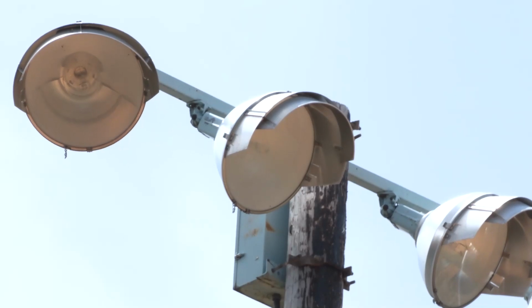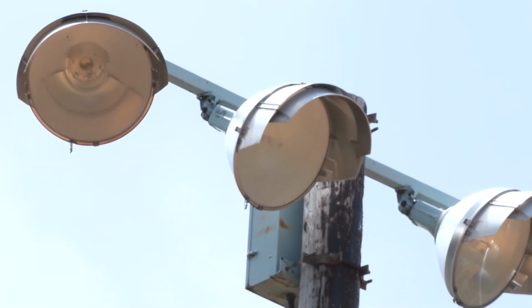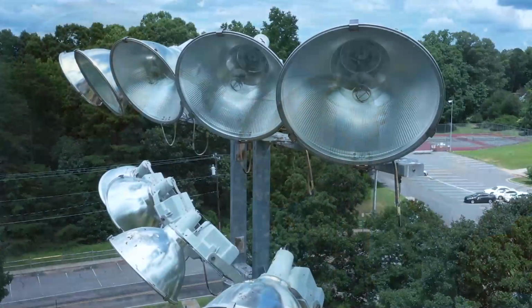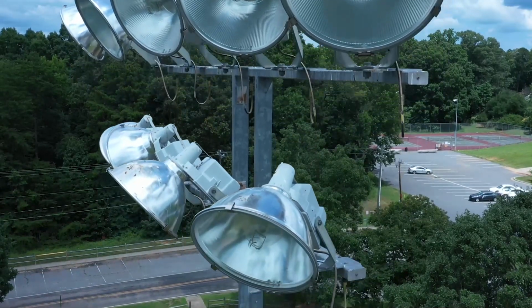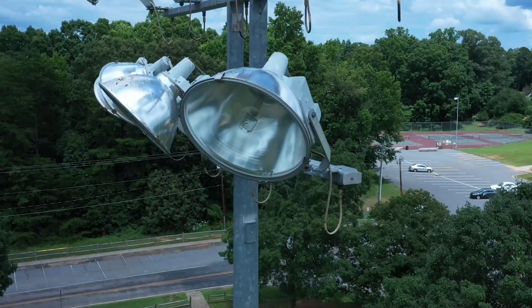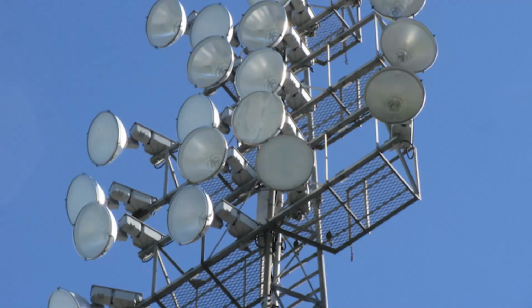When you start the visual inspection of the fixtures, look for any cloudiness on the lenses, which can result from dirt or gases inside the optics that cloud the inside of the fixture. If your lenses show sign of cloudiness, it could block light output and affect your light levels on the field. Additionally, water can seep into the luminaire housing, which should be visible from the ground level.